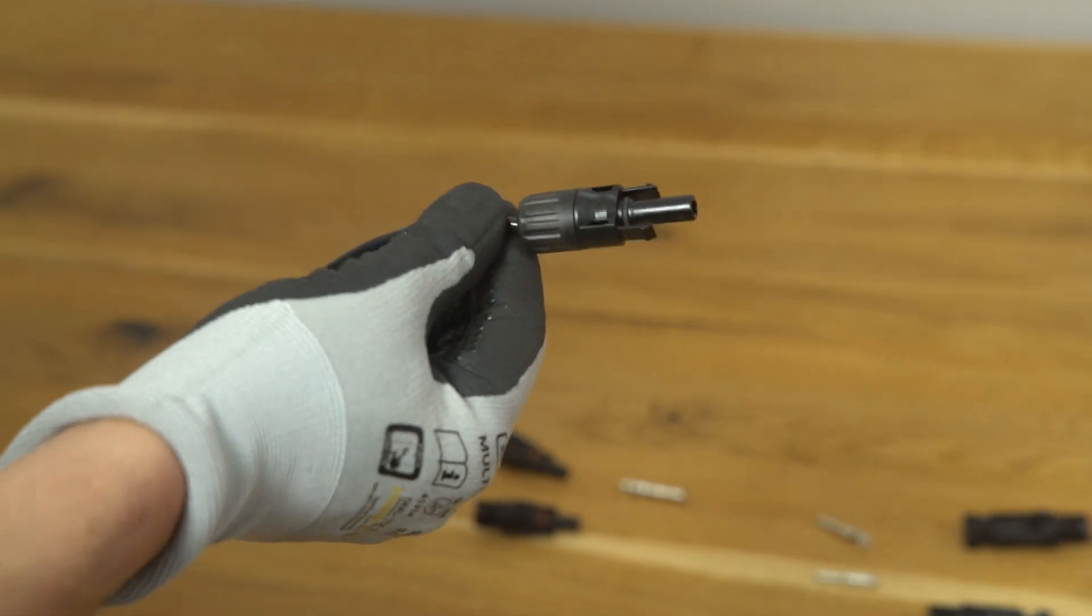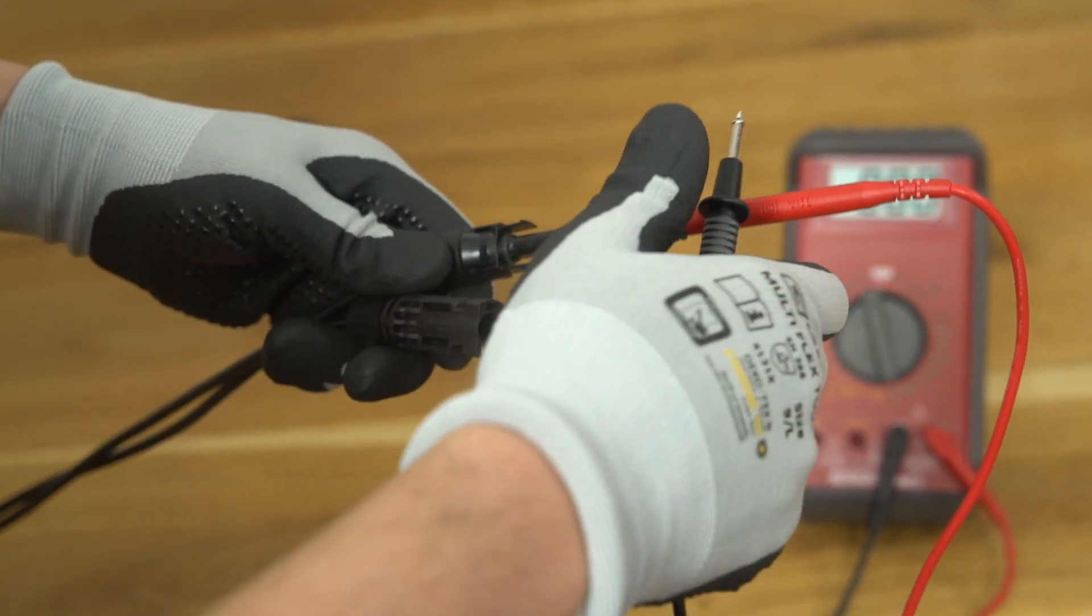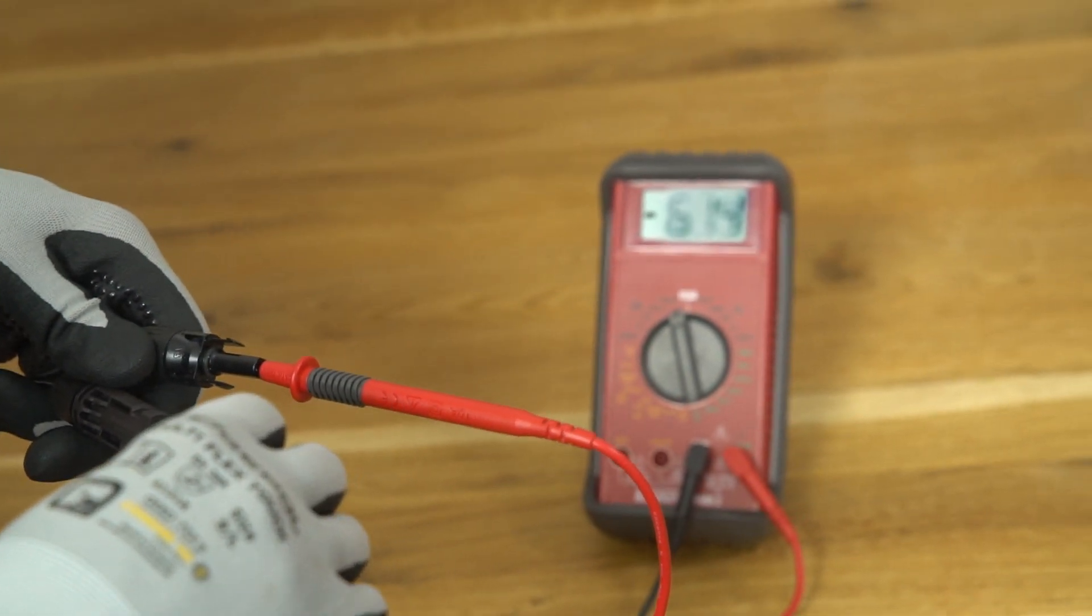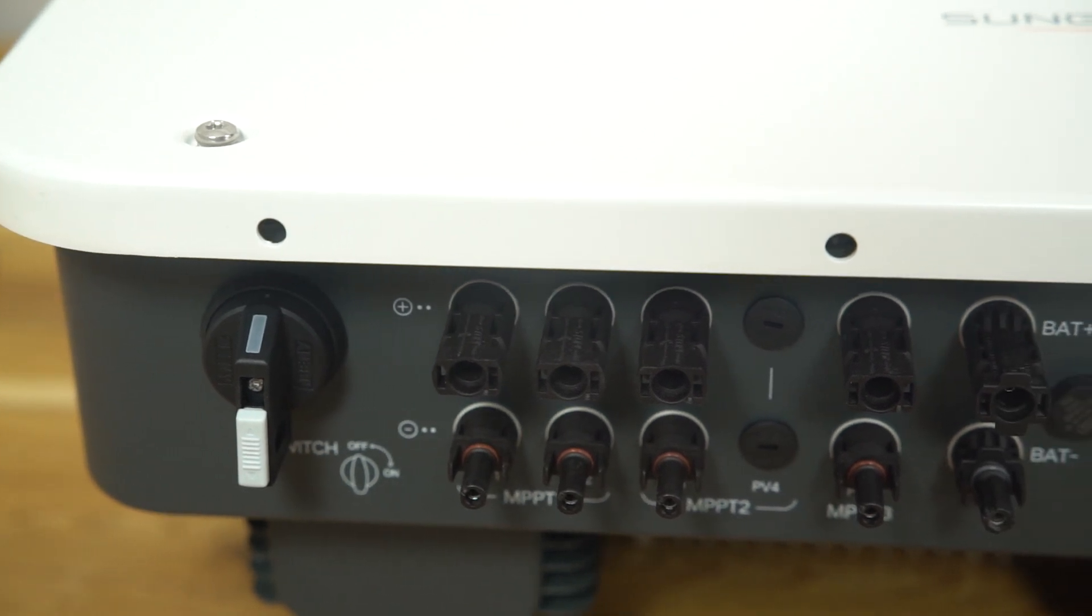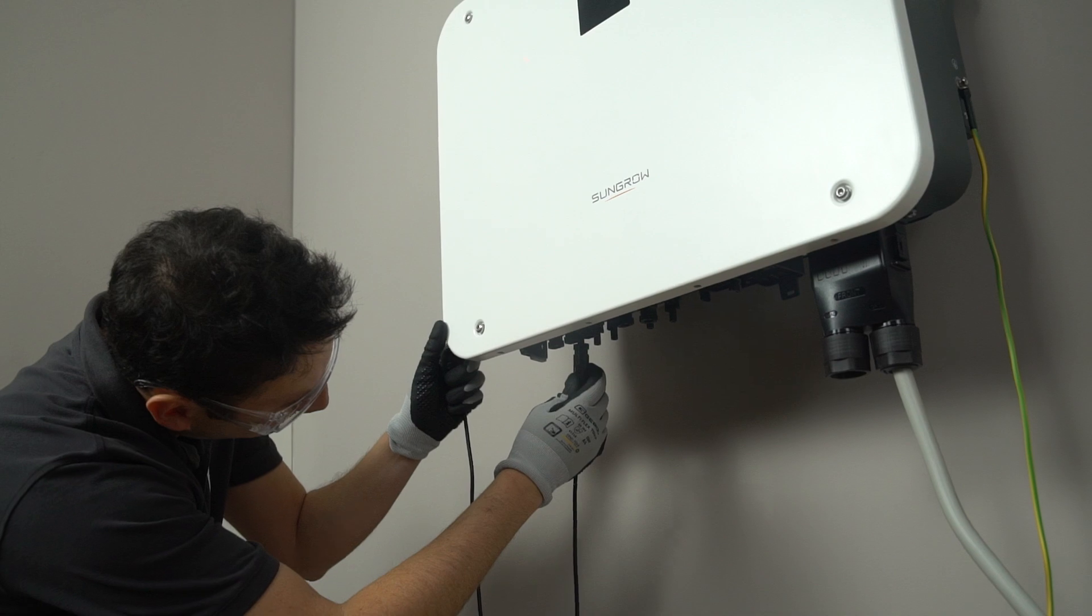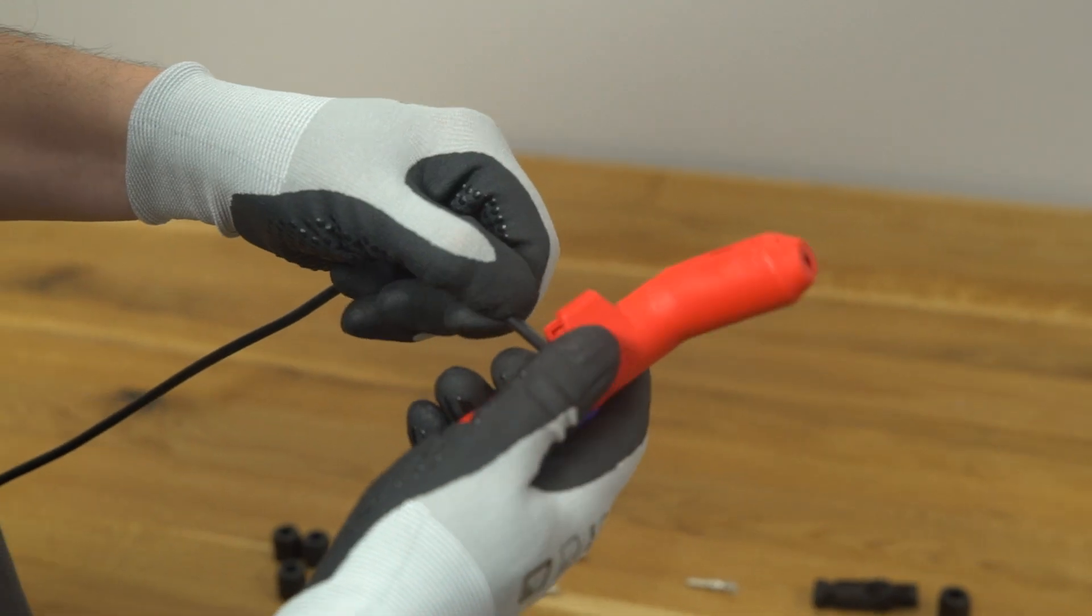Check the DC cable connections for polarity correctness. Ensure that the open circuit voltage in any case does not exceed the inverter input limit of 1000 volts. The polarity is marked on the inverter. Check again that the polarity corresponds to the imprint, then plug the connectors into the right terminals. You will hear a click when you connect the plugs to the connections on the inverter.